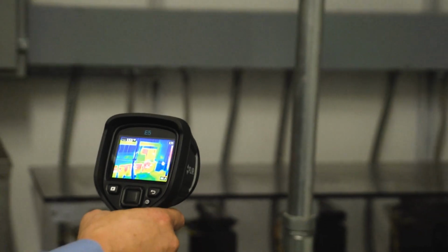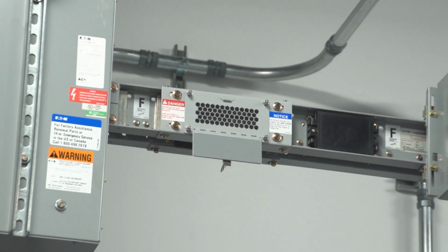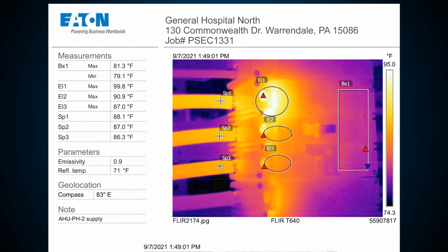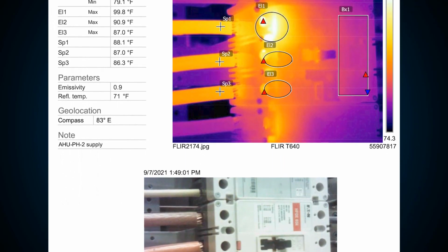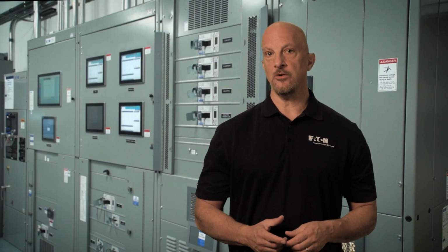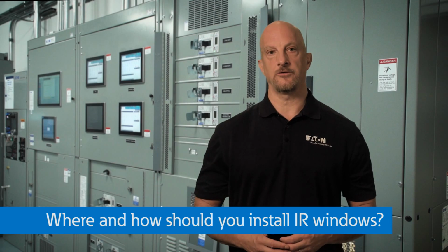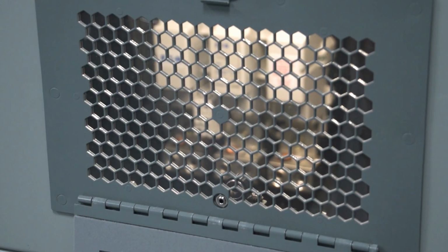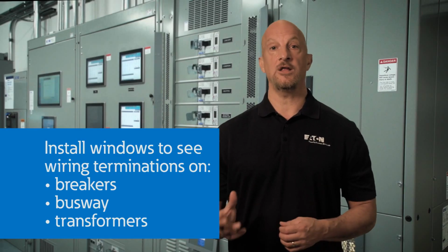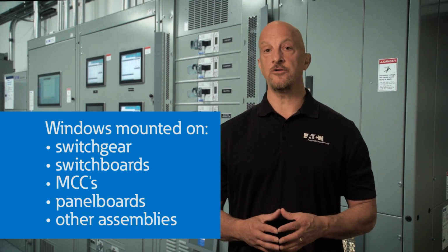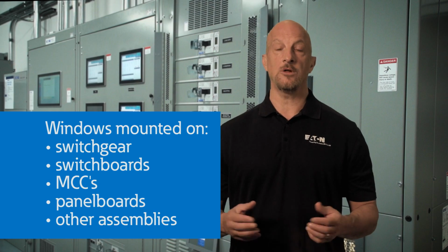So today, with the right camera and taking advantage of the latest technology and innovations, IR windows strategically placed on the equipment can allow you to do scans without having to deal with the arc flash or shock hazards. You can obtain the data you need safely and efficiently, and you can actually do the testing more frequently, thereby giving you a better chance of preemptively finding thermal problems on your equipment. Once you've established that you need windows, where and how should you install IR windows? For new equipment, consider installing IR windows capable of showing the wiring terminations or connection points on breakers, busway, and transformers. This can include windows mounted on switchgear, switchboards, MCCs, or other assemblies.